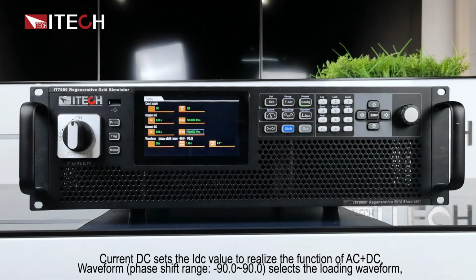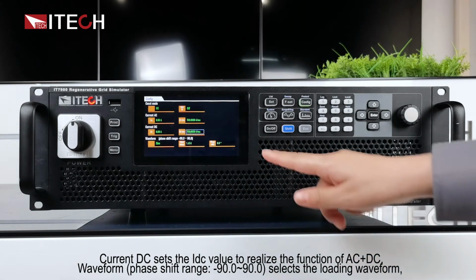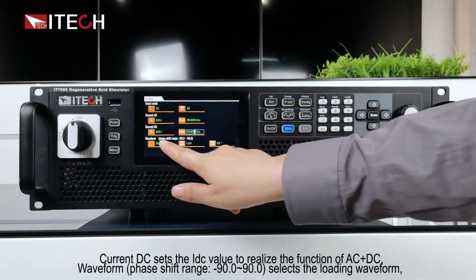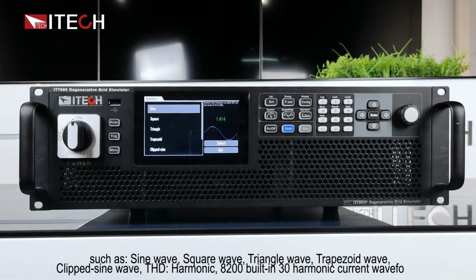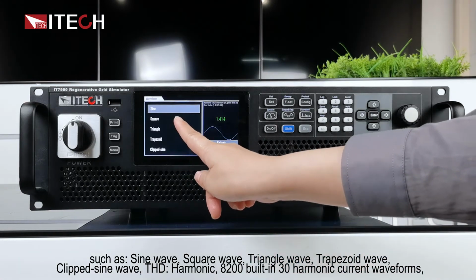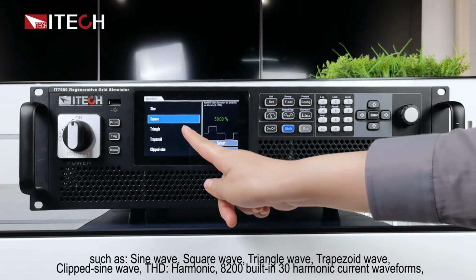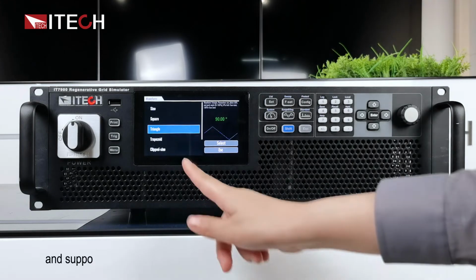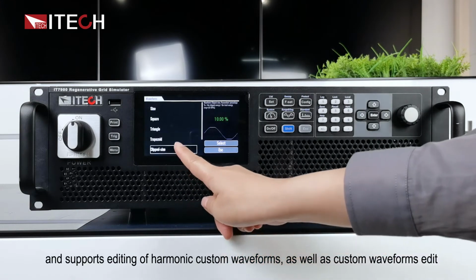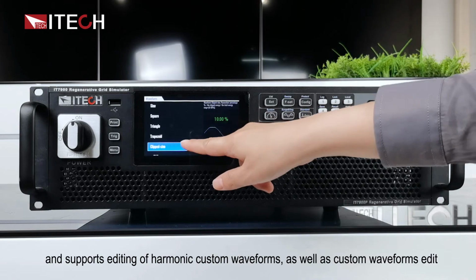Waveform, phase shift range -90.0 ~ 90.0, selects the loading waveform, such as sine wave, square wave, triangle wave, trapezoid wave, clipped sine wave, THD, harmonic. 8200 has built-in 30 harmonic current waveforms, and supports editing of harmonic custom waveforms, as well as custom waveform edit.